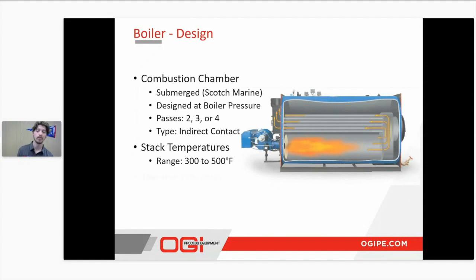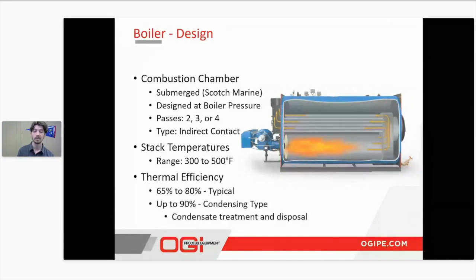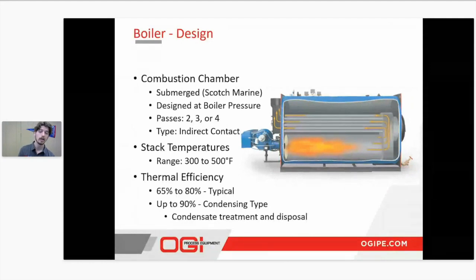As well, the thermal efficiencies are going to vary based on the number of combustion chambers, the number of passes, and that exhaust stack temperature. And then additionally, conventional boilers are typically going to require an external heat exchanger, especially in an NSF type situation where you can have that direct contact with it. Each different heat exchanger interface that you're going to be incorporating there is going to lower that efficiency slightly whenever it gets to your actual sanitation stations.